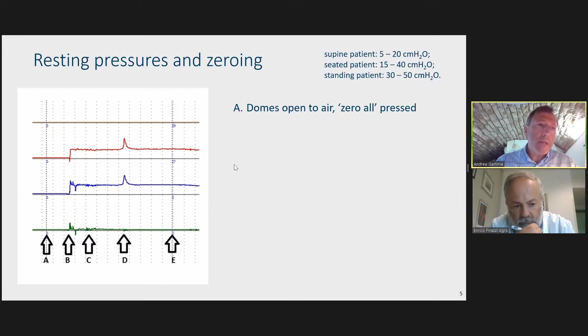To start with, we've got at point A, the domes or the transducers are all open to air, and you press 0, which means that you are zeroing to atmospheric pressure. That's the standard, as I'm sure you're aware. Then when you reach B, the pressures come up because you've opened the catheter to the patient. The tap has been moved or whatever your system is.